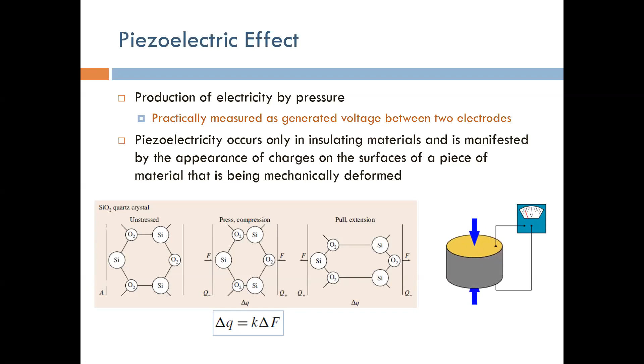What you do is send a pulse of ultrasonic wave, which is basically like a pressure or voltage waveform. The piezoelectric material converts voltage to pressure and pressure to voltage, so it works reversibly between the two — it can go from voltage to pressure, or from pressure to voltage. So you apply a voltage waveform to create a pressure wave, and this pressure wave goes outside.